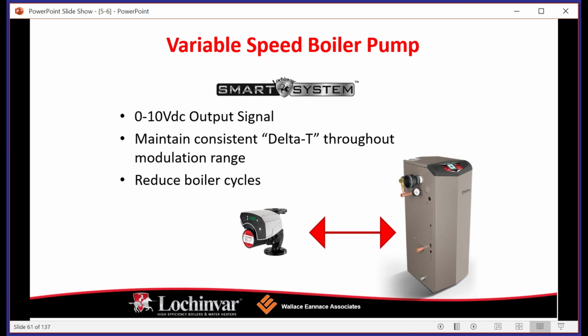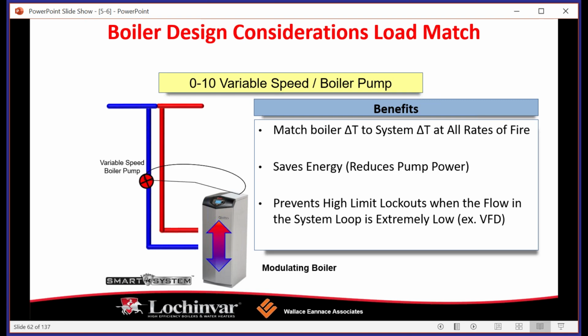Now, variable speed pumps with ECM motors are going to be regulated or required by law within the next handful of years, right? Because of efficiencies, right? The ECM motor requires a magnet to start. It doesn't have as big a max inrush. It doesn't require as much energy to run. But for our purposes, the modulating variable speed pump is important because we are going to match the delta T of the boiler to the pump flow through the entire fire rate. Now, this ties back to turndown, right?